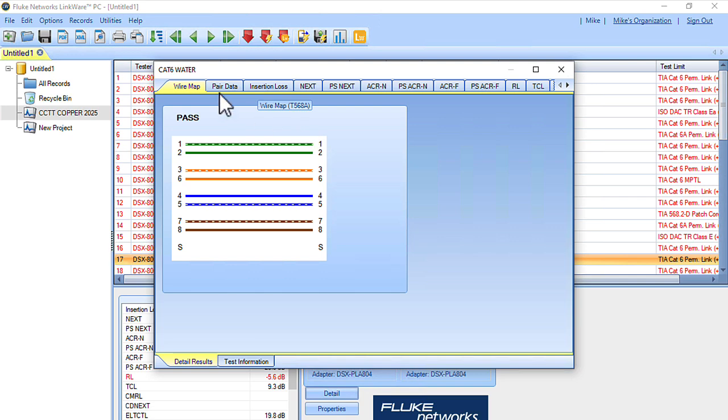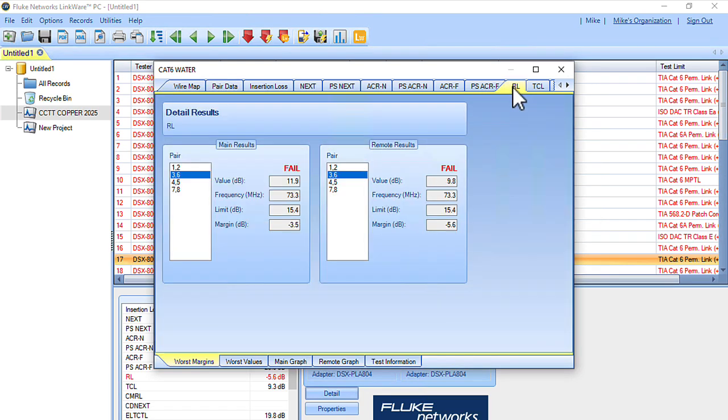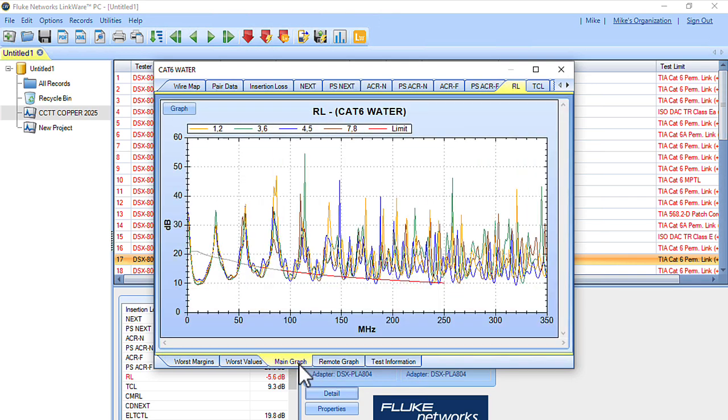we can take a look at pair data, we can take a look at our return loss, we can look at our graphs, and the graphs are a big one for troubleshooting. This will give us an indication of what's going on with that cable.